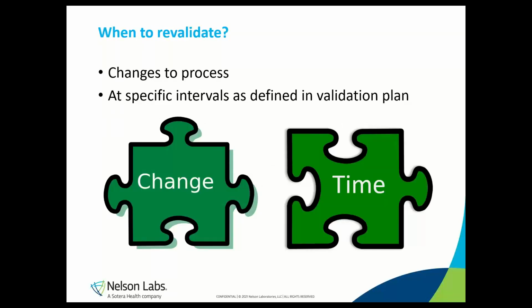When should you revalidate? Well, anytime you make a change, big or small, you need to assess what impact that change will have to your validation and address whether additional testing or revalidation is needed to confirm that the change did not affect the original validation or your process output. Some changes may be covered with just a paper assessment. Some may need an assessment and some confirmatory testing to show the change did not have an impact. Some changes may require the whole validation to be repeated.